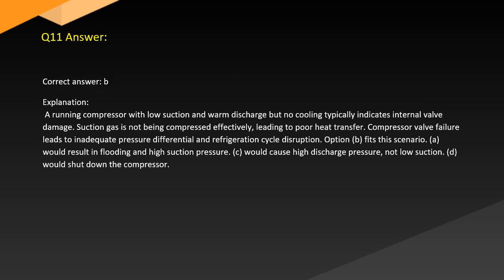Answer. Correct answer: B. Explanation. A running compressor with low suction and warm discharge but no cooling typically indicates internal valve damage. Suction gas is not being compressed effectively, leading to poor heat transfer. Compressor valve failure leads to inadequate pressure differential and refrigeration cycle disruption. Option B fits this scenario. A would result in flooding and high suction pressure. C would cause high discharge pressure, not low suction. D would shut down the compressor.